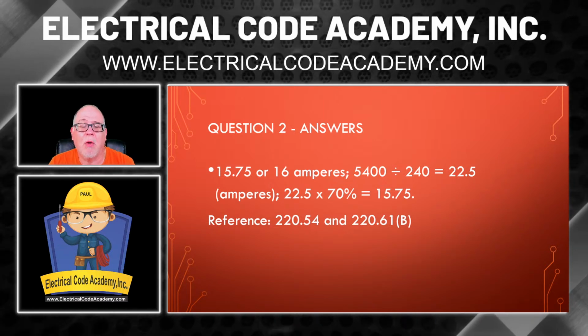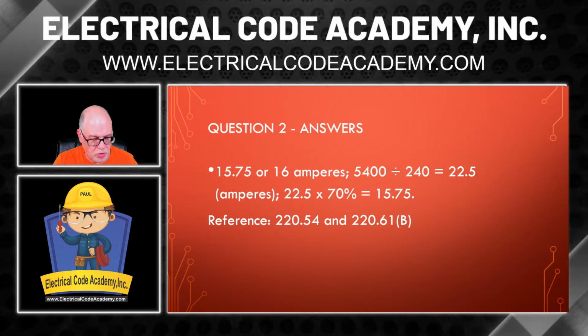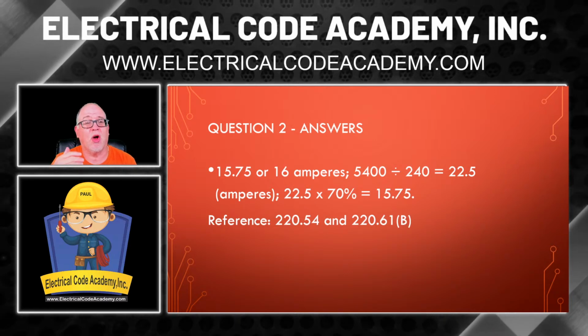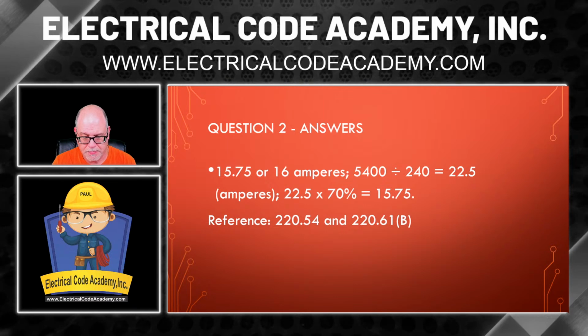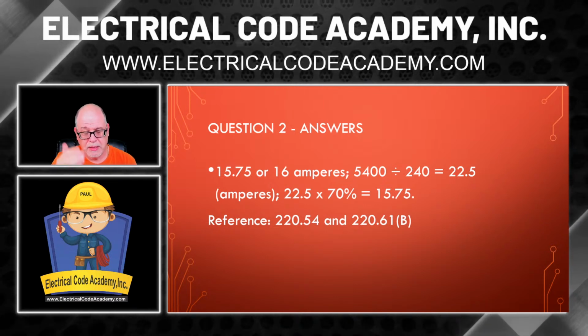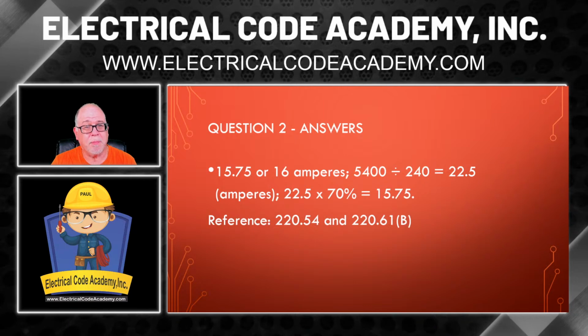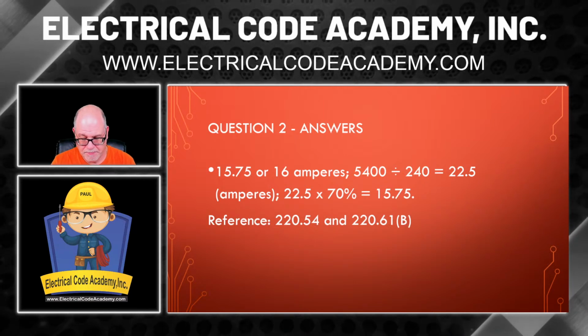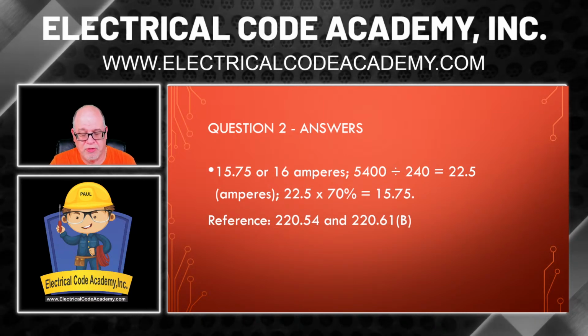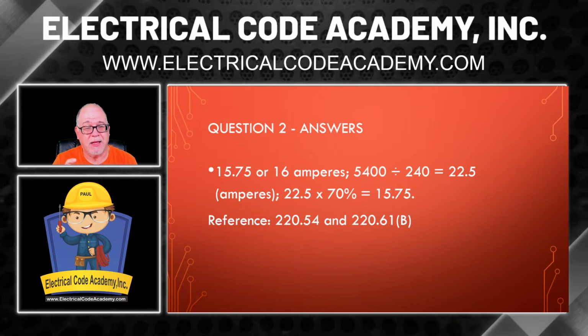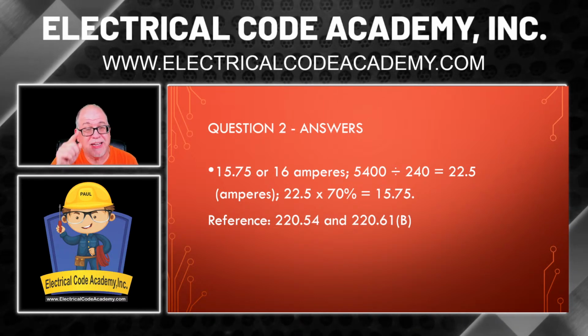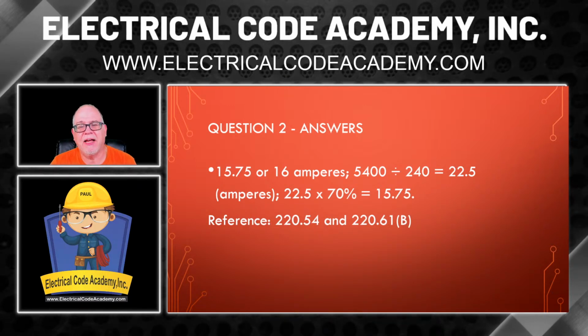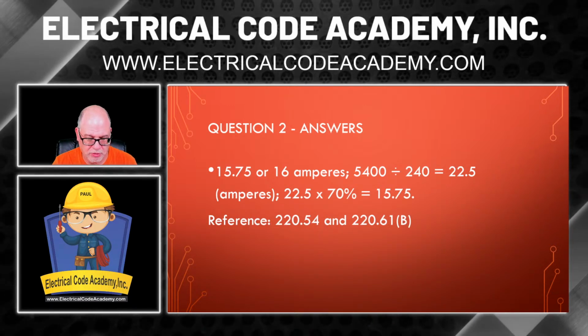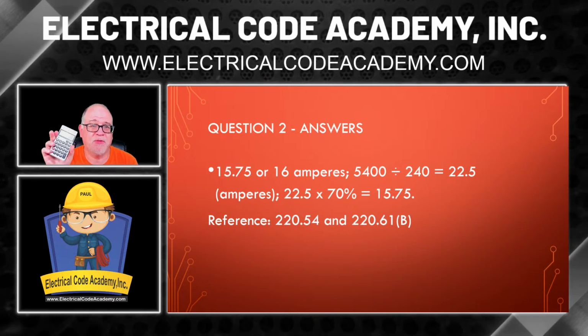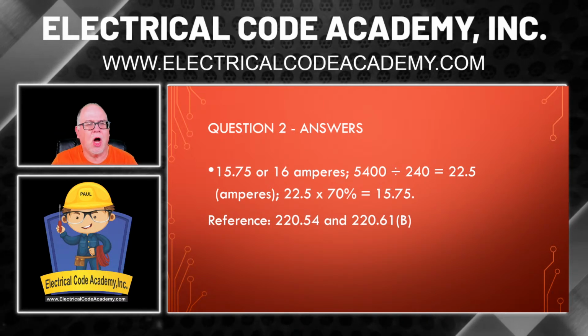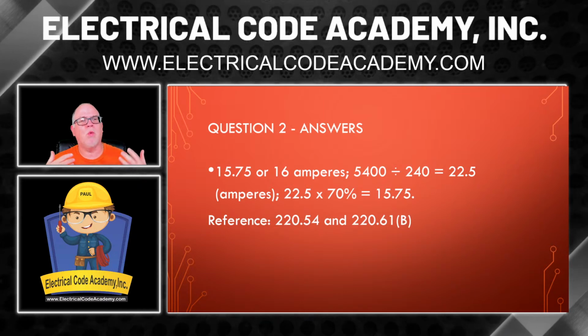Now, I want to talk about the other way you could have done this. One other way is to start with our full value, our 5,400, and multiply that by 70%. That gives you 3,780 VA. Then you could take that and divide that by 240 volts. And that also gives you 15.75. Always remember, there are many ways that you can do this.